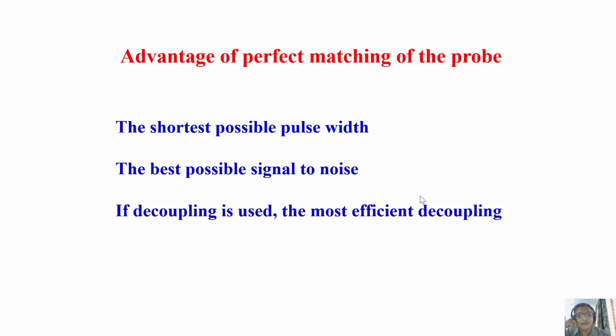Another advantage of matching the probe: if I don't match properly, what happens? The shortest possible pulse will be there if you match it, because you are putting in full power and the entire power goes to the sample. Otherwise, you think you are applying some power, but the majority of the power comes back as standing waves or reflection, so the sample will not feel full power. So, for a 90-degree pulse width of 5 microseconds, let us say you need only 30 or 40 watts of power. You may have to use double that because the entire power is not going inside. That is a disadvantage. That's why, if it is matched, you can get the shortest possible pulse width.